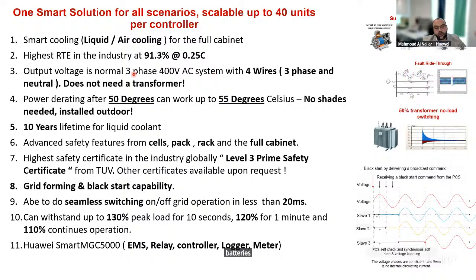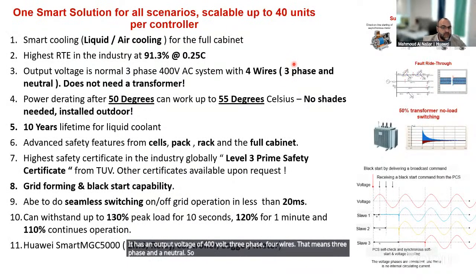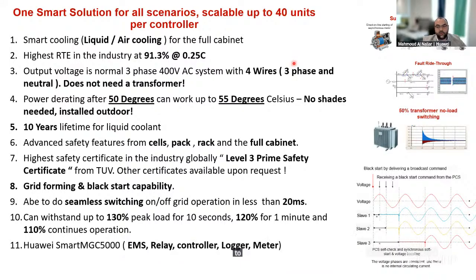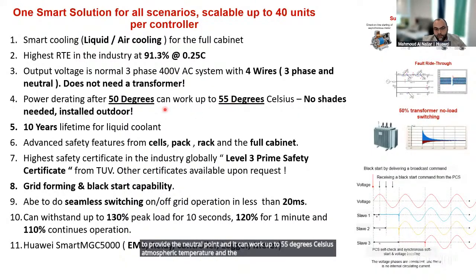It has an output voltage of 400 volt, 3-phase, 4 wires. That means 3-phase and a neutral. So you don't need to install any external transformer to provide the neutral point. And it can work up to 55 degrees Celsius atmospheric temperature, and the derating starts only after 50.